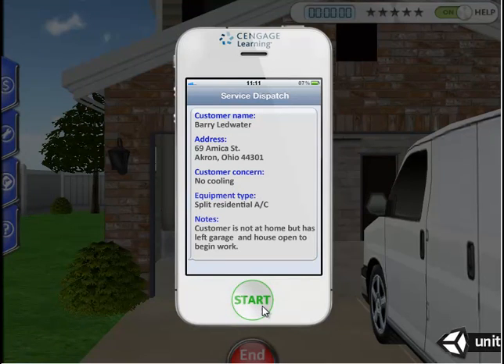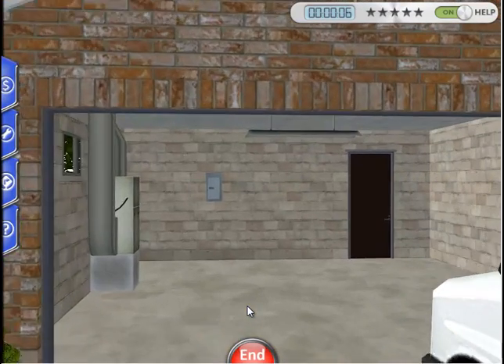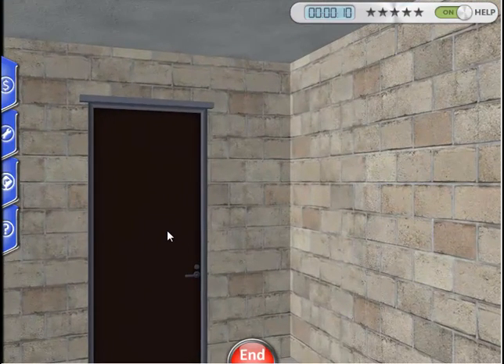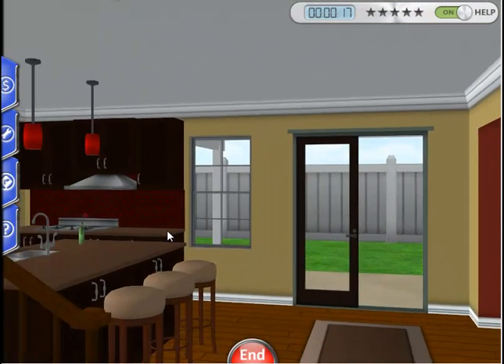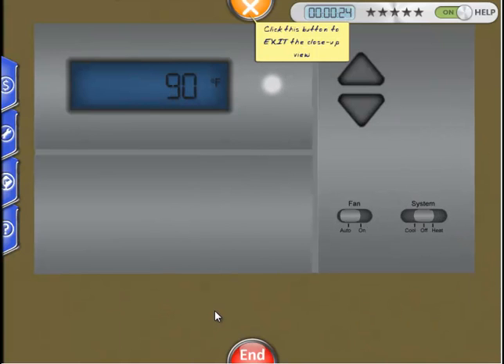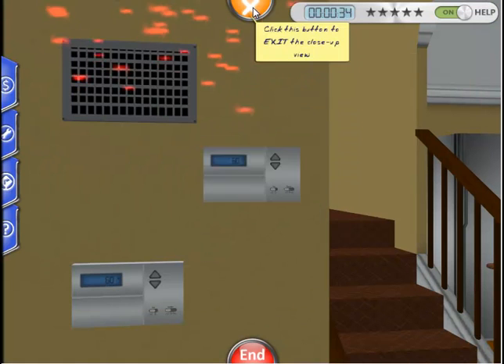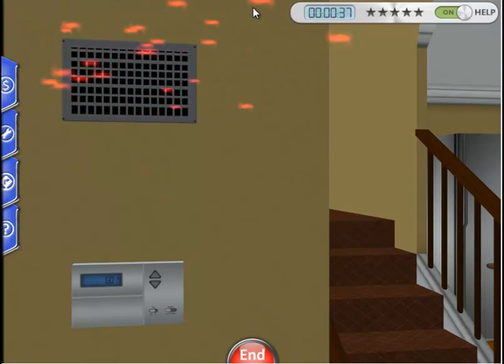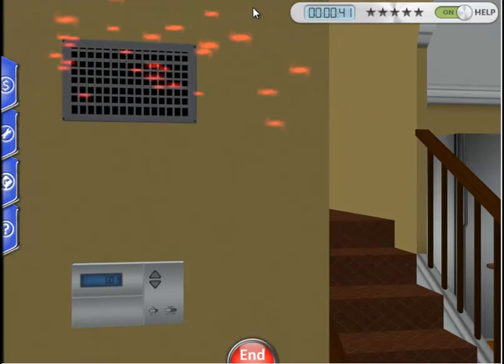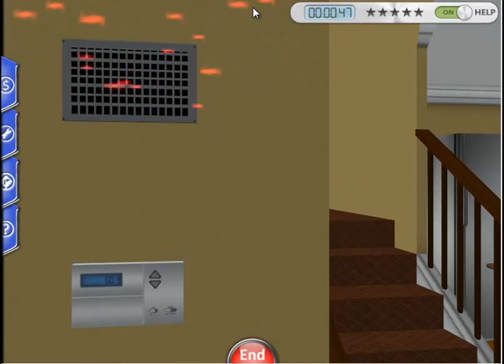Our smartphone indicates that the customer has no cooling. We will first go inside and take a look at the thermostat. To move, use your arrow keys on the keyboard. Click on the door to open it. The thermostat is to our immediate left when we walk in. Let's click on it to get a closer view. Now let's turn it to Cool. Note the thermostat is set for 60 degrees and the original temperature was 90 degrees. Let's exit the thermostat by clicking the orange X button. The red particle animation coming out of the supply duct indicates that the air conditioning is not working and is blowing hot air into the living space.